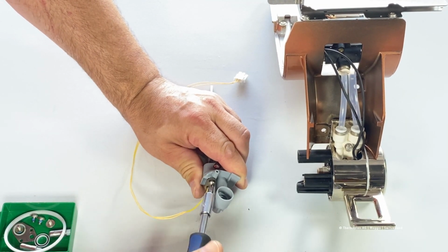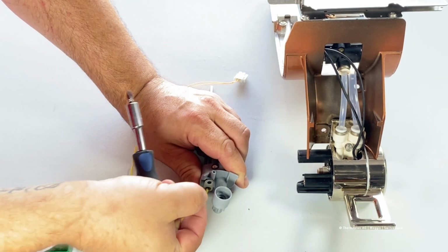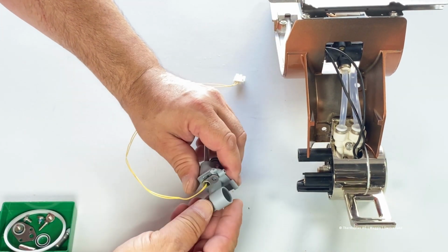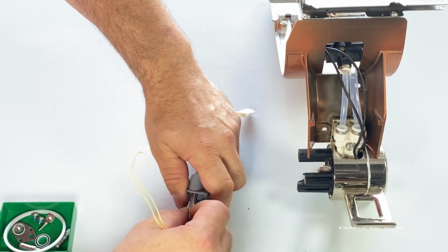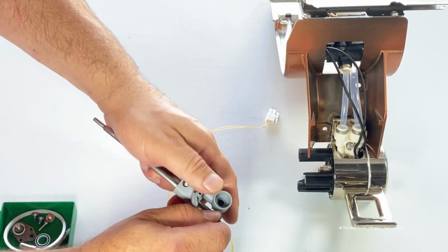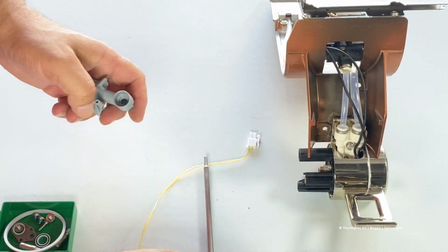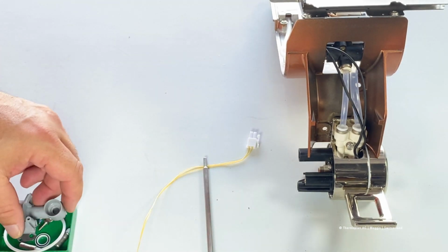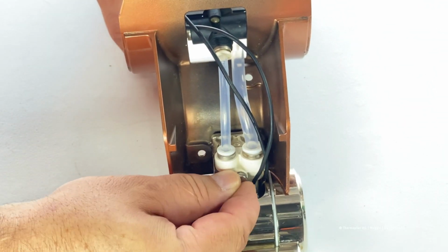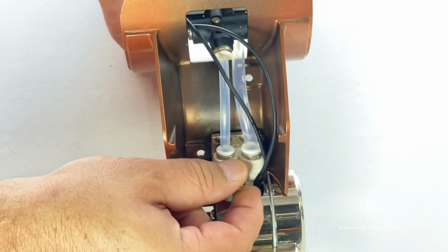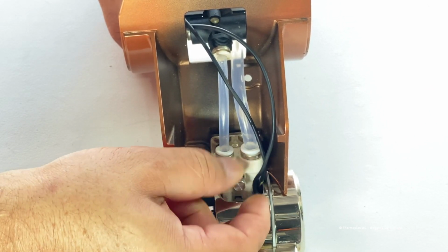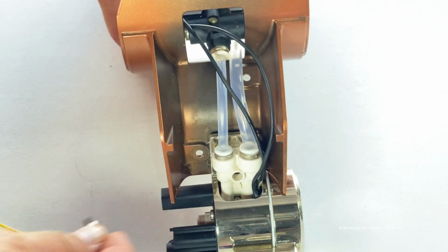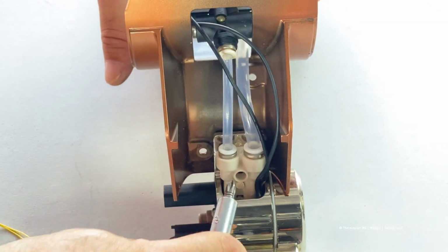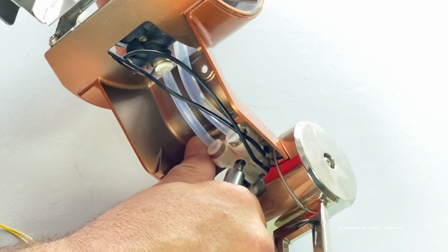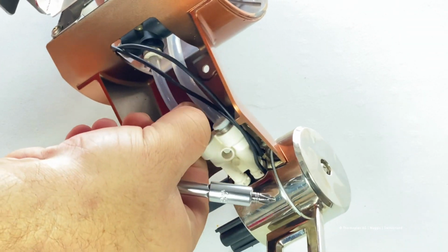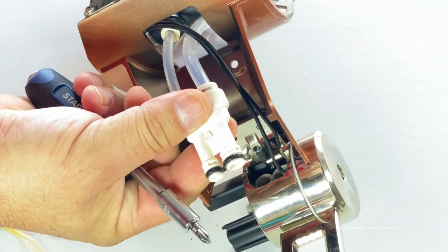Then from this plate I take off one screw which holds the NTC probe on that steam connection piece. Then I can slide it out. If you need to take out this connection piece, there's a thumb screw. Make sure you don't pull the piece out on the hoses. Take a screwdriver and pull it like this. After, it helps to put some 111 Molykote on the O-rings.